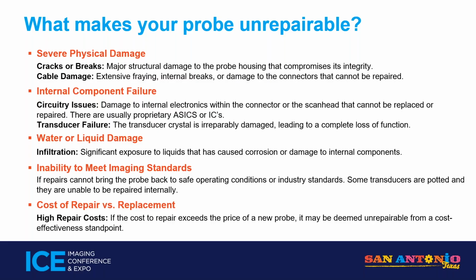Cost of repair versus replacement - at some point you have to make a decision: is it more effective to repair it or replace it? If it's array damage, a new array costs as much as a probe, so you might as well get a brand new probe or at least a refurbished one, because it's not cost effective to repair just the array.